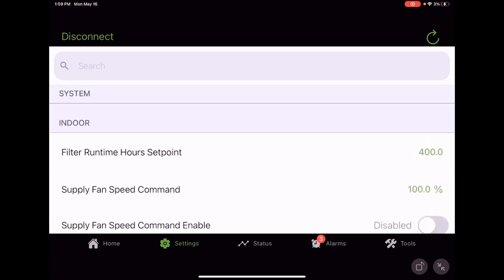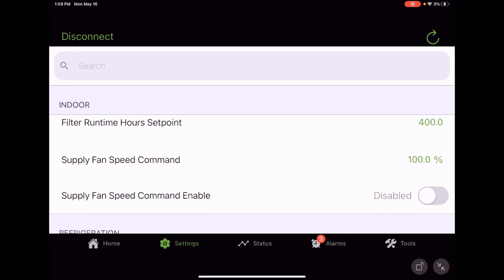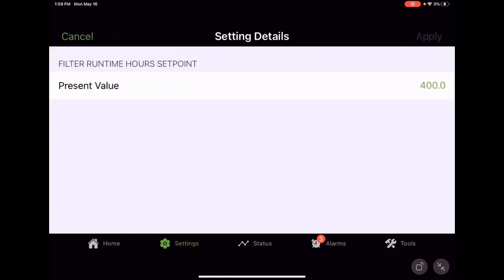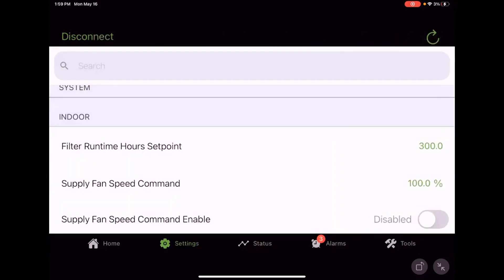We can come over here and make some adjustments to things like filter runtime. Well, maybe it doesn't take 400 hours for our filters to get dirty. Maybe it only takes 300 hours, and at that point in time we're going to go ahead and get that filter runtime diagnostic or informational diagnostic.